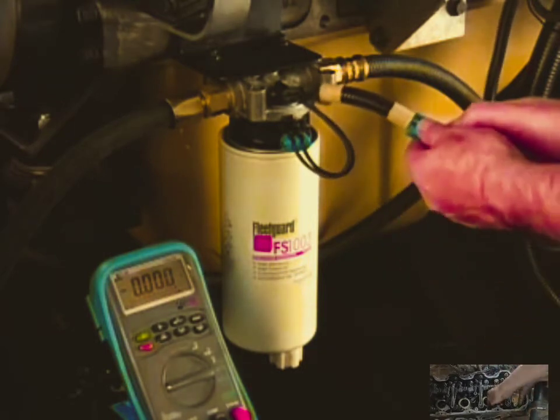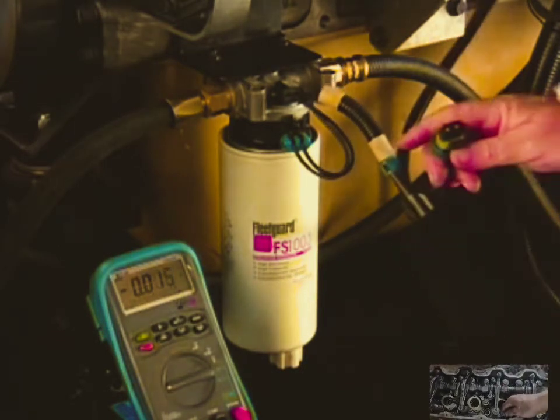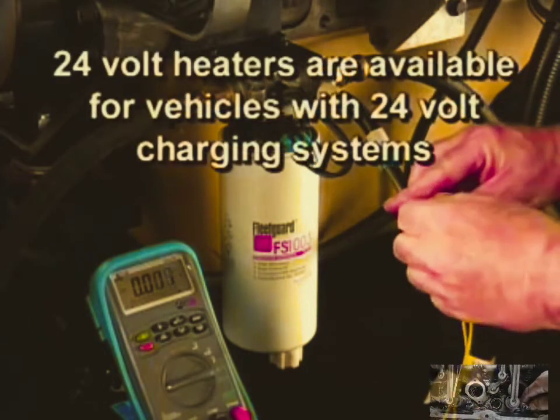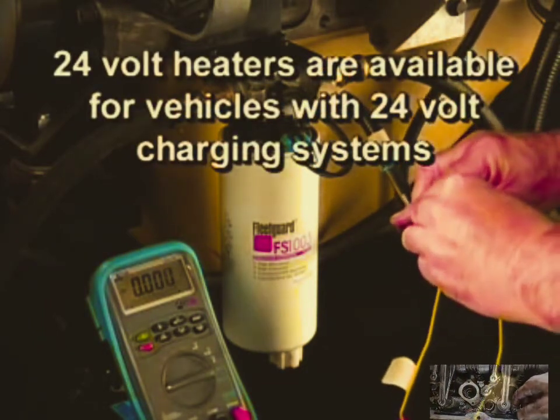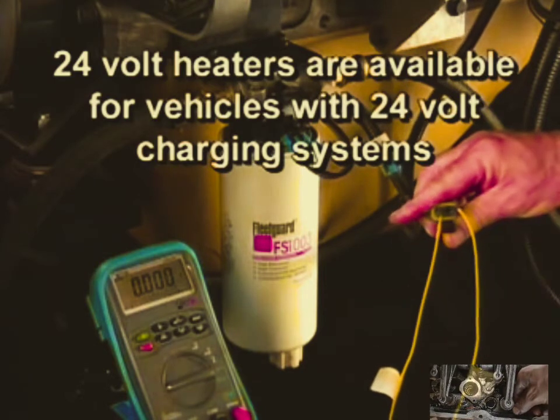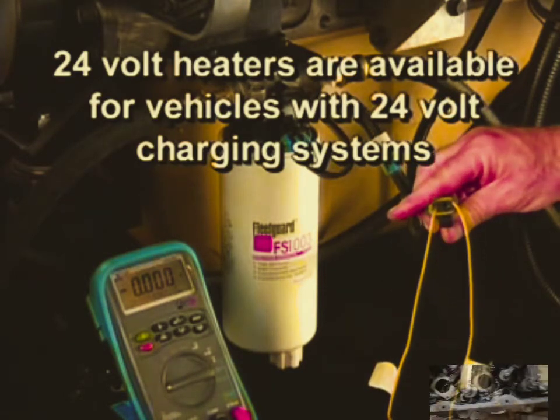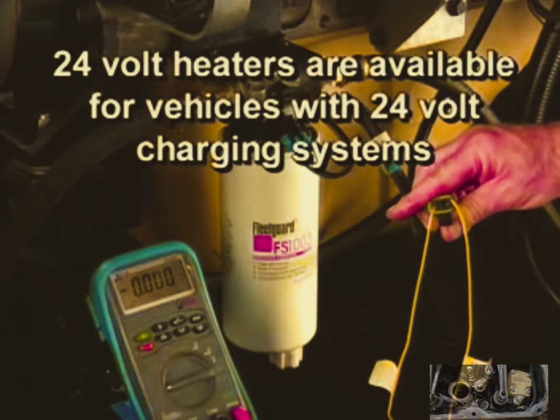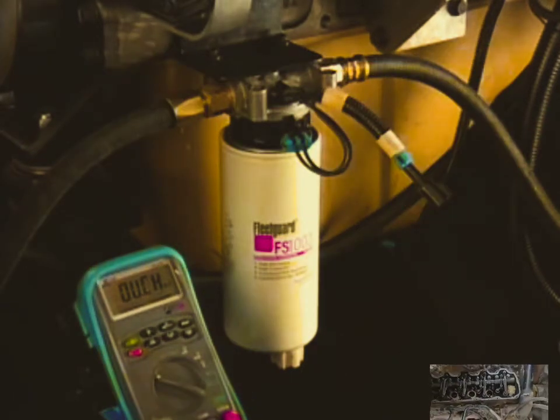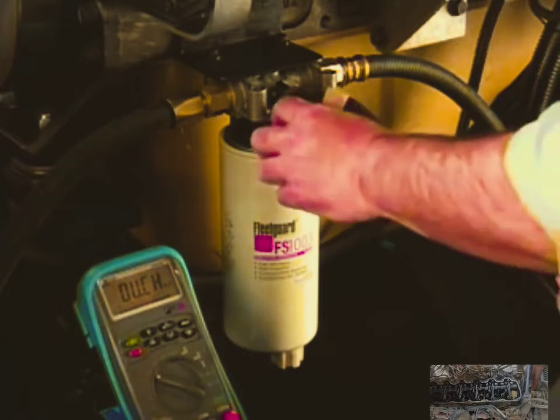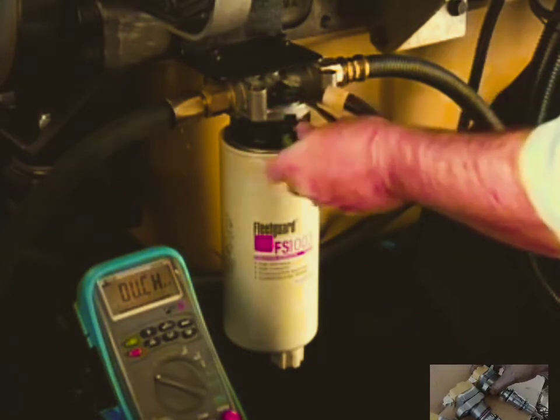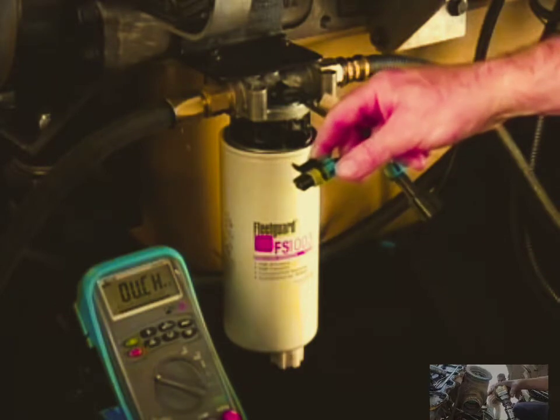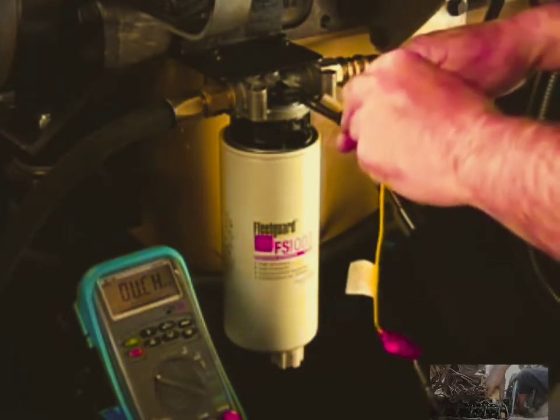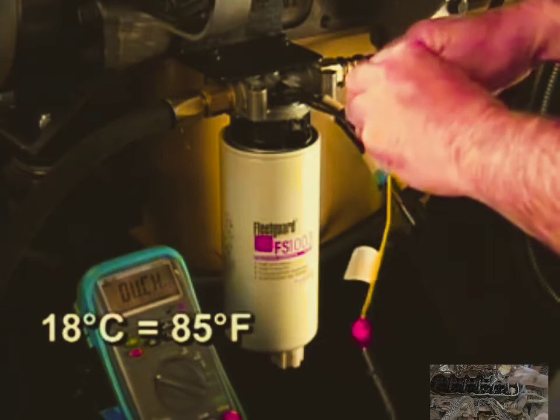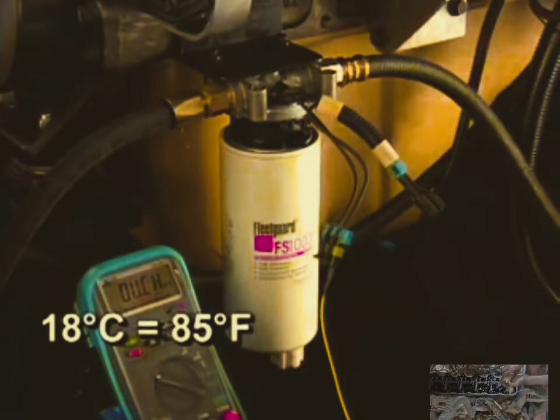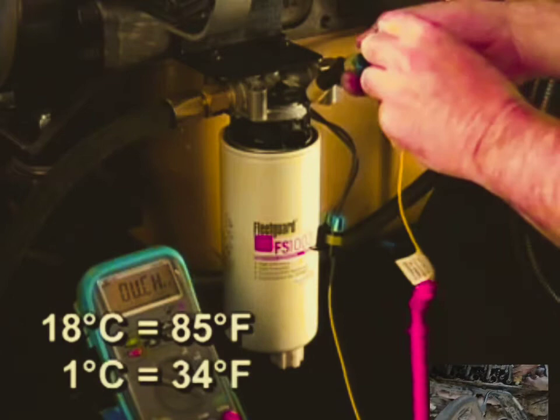With the connector removed and the key switch on, power supply to the heater must be at least 12 volts. If the voltage does not meet specification, refer to the OEM repair manual. The fuel heater is switched on and off by a bimetallic switch at the filter head. Test the switch with an ohm meter. It should register as open, high resistance, above 18 degrees centigrade, and register as closed, near zero resistance, below 1 degree centigrade.